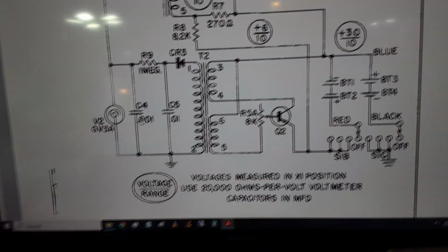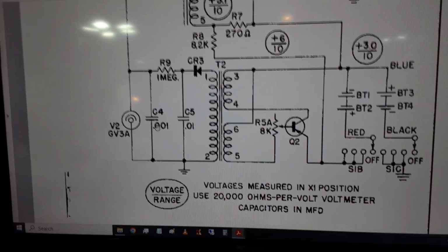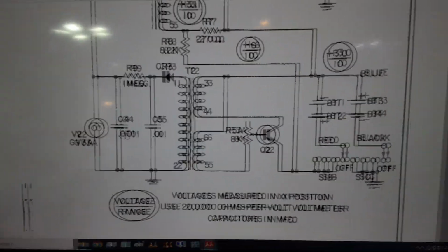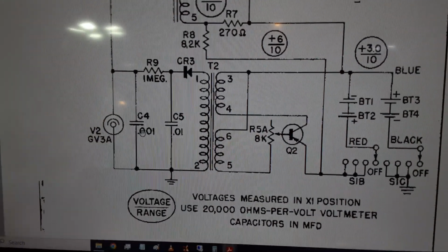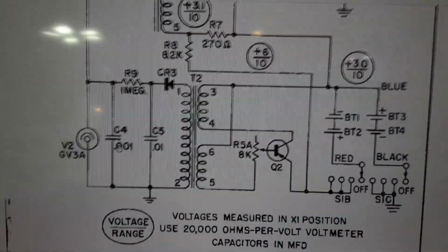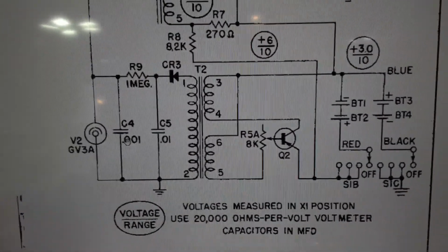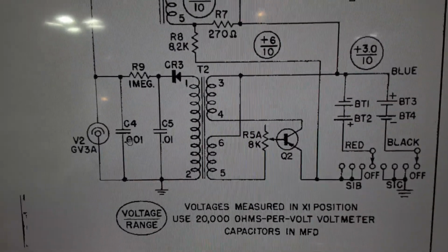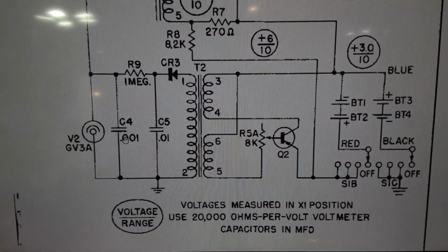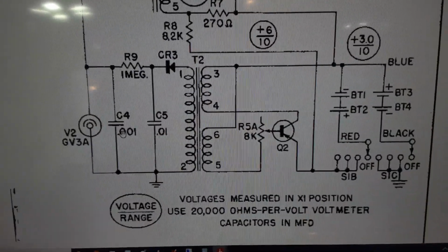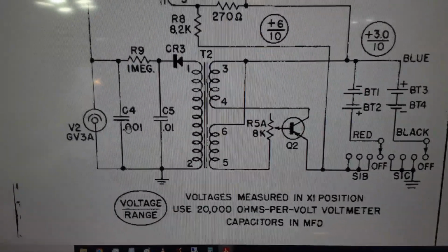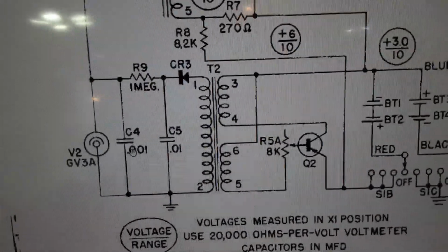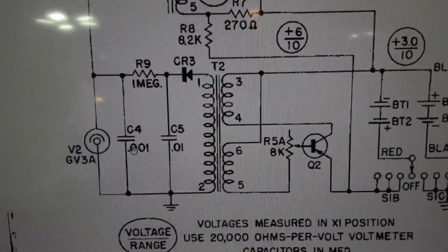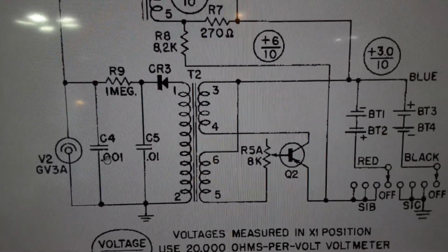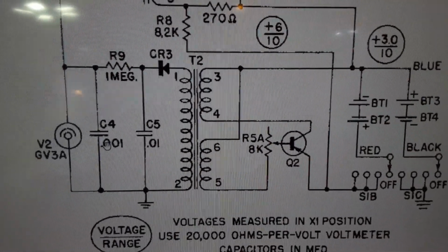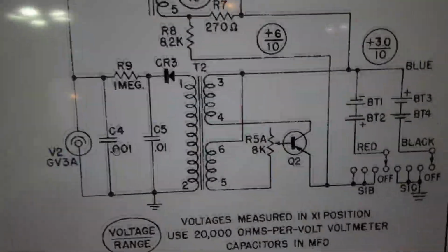And there's two ways I know. One, there's no sound. Two, there's no evidence of any voltage on this side at all of this transformer, this flyback transformer. The other thing is, it is a flyback transformer, which means if it was pulsating and turning on and off, the iron core would vibrate, and you would actually hear that. You should hear some sound as the core is vibrating. However, whatever frequency it's vibrating at, it's going to be low frequency, probably around 200 hertz. So you ought to be able to hear those laminations in the transformer actually vibrating and clicking against each other. And there's none of that.